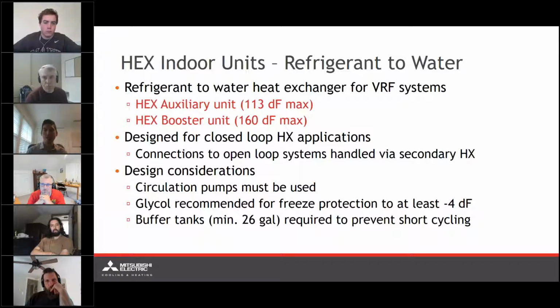Now, the closed loop system serving the HEX or the booster unit should also be chemically treated with corrosion and rust inhibitors and a balanced pH. Ultimately, we want to make sure that the water running through these is not going to eat away at the pipes themselves. We're going to have healthy water in here. Especially in this particular climate, we're going to want to make sure that we have glycol for freeze protection down to at least -4 degrees. Also, since these units are intended for closed loop applications, we need to apply circulation pumps in order to circulate the closed loop heat exchange fluid, water in this case, through the unit. During the design process, we want to make sure that pressure drops and flow rates and all the equipment this is going through, all the parts, are taken into consideration.